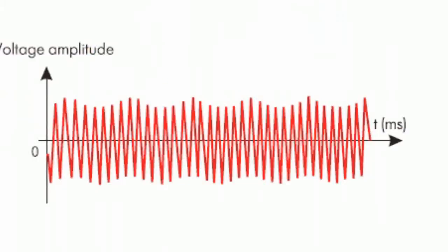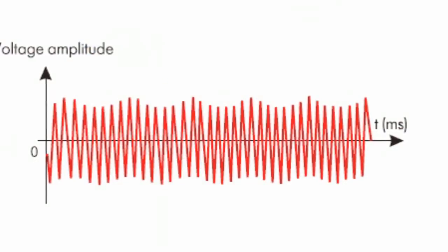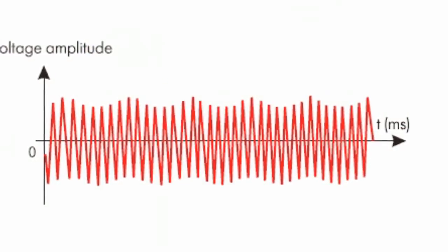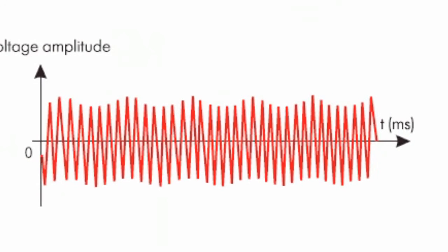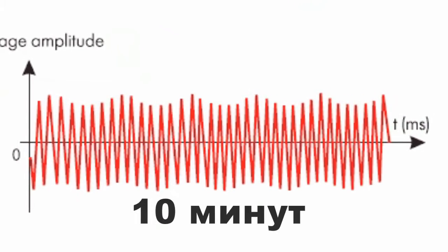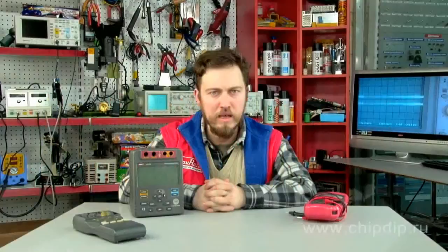Moreover, since we don't know the reason for a flicker effect caused by a particular load, the immediate flicker effect value might change considerably and unpredictably throughout the measuring period. A measuring period of 10 minutes is a fair compromise. It allows determining the value of the short-term flicker effect.